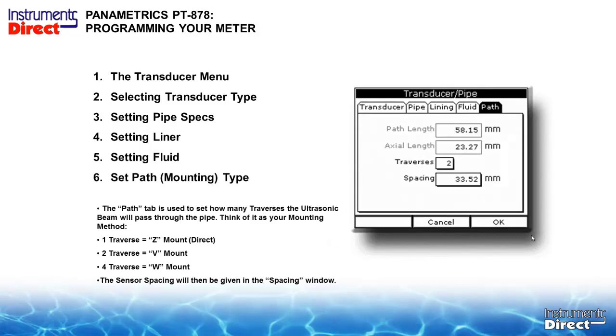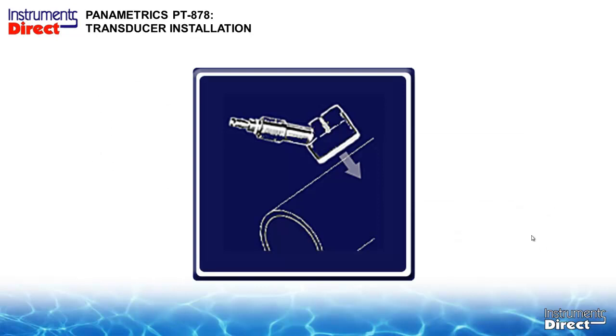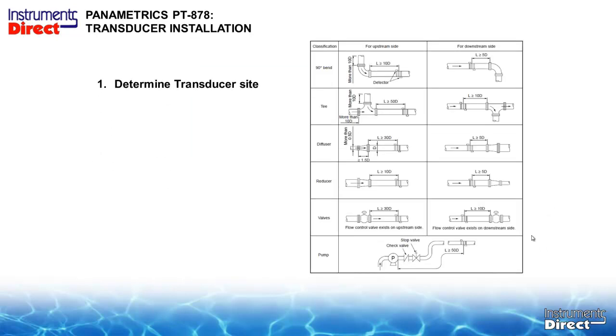Now we're going to select the path. On the path there, remember again, we can select a single traverse, which is a Z mount, one on each side, or the V mount configuration, which is both on the same side. Again, most of you will be using the two traverse, which is the V mount configuration. And then the device will give you the spacing and where to locate the transducers. As we said, you want 10 to 15 pipe diameters downstream, more if you have obstructions like we looked at before. Get away from those special connections, get away from pumps, get away from tees, reducers, and any invasive thing inside your pipe.